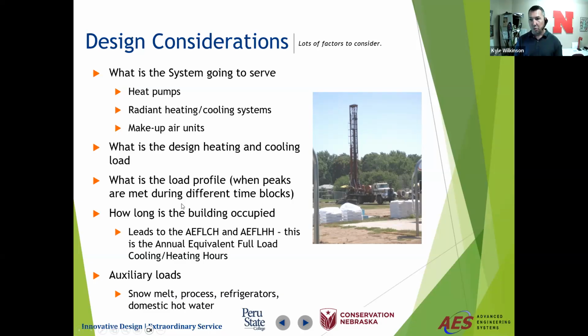So all the different design configurations, it's not just like a rule of thumb thing. So we have to go through different calculations. We look at the load. What's the heating load? What's the cooling load? Is it heating dominated? Is it cooling dominated? What's the load profile? Does it spike really high and go down, or is it more constant? All these affect how you're trying to use that energy from the ground.